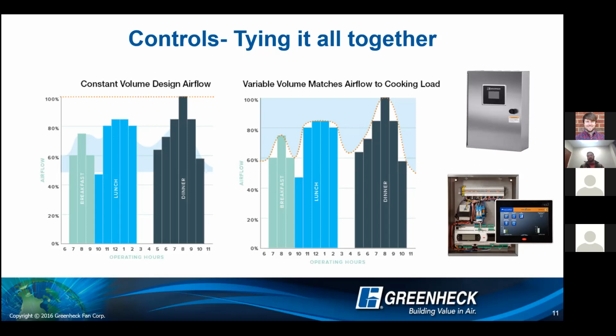Our minimum set point is typically 92 degrees Fahrenheit. So when our temperature sensors sense 92 degrees Fahrenheit, even if the cook has not turned on the hood, maybe they just came in, turned on their appliances, and went to the back and started doing prep, the kitchen system is going to come on per code, and that's going to happen because of the temperature sensor.